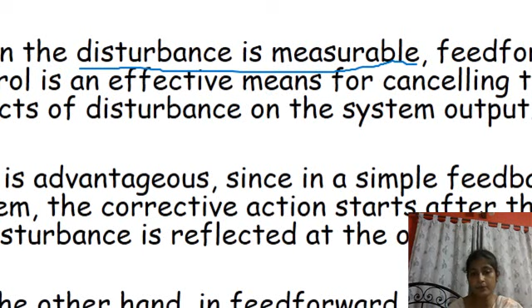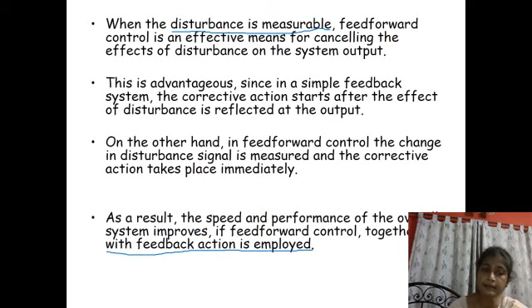But for a real feed forward control system, the feed forward control is always used along with feedback control system. The real feed forward control system is always used along with feedback action. This is because for feed forward control we need to develop a mathematical model so that the energy adjustment should be such that error is corrected before reflecting to the outlet. Now this is again a mathematical model, so there must be certain error. So if any deviation is reflected at the outlet, then feedback action will take care of that error elimination.